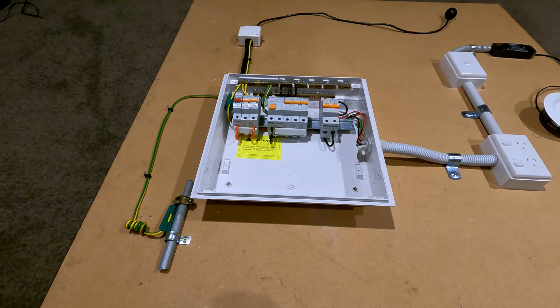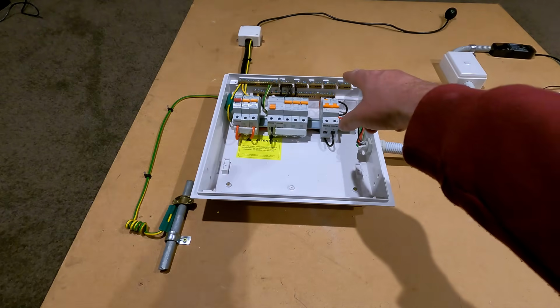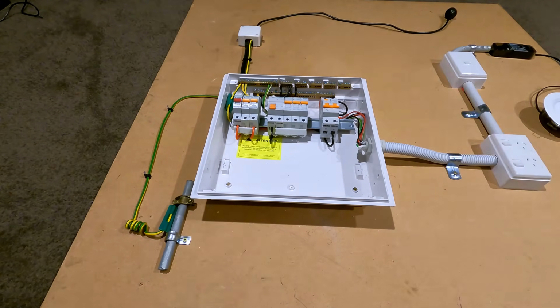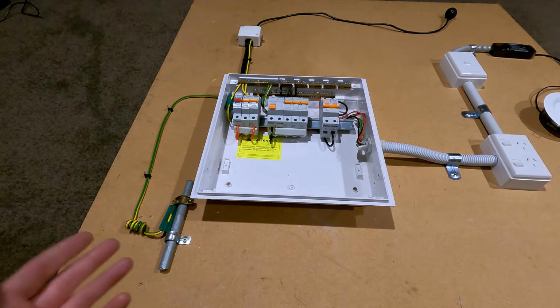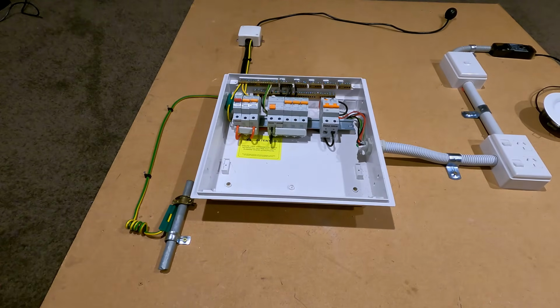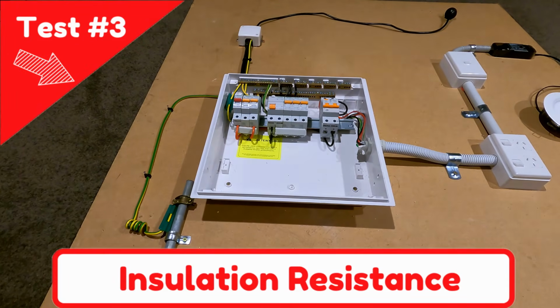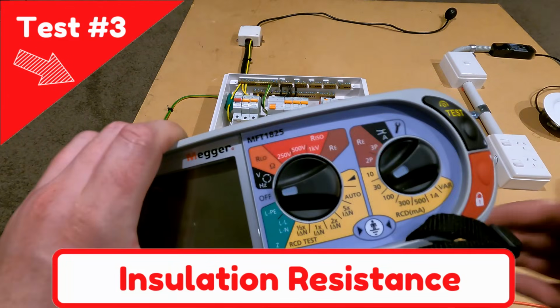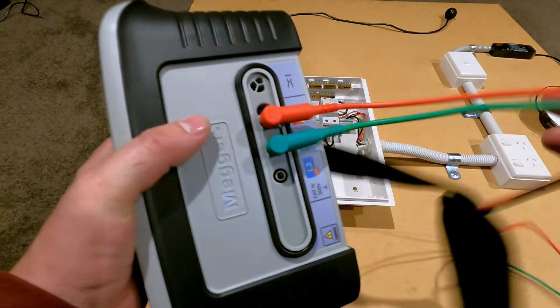Now that's the only thing I don't have set up. I could have used one of these RCD bars as an equipotential bond, but it's the same process. Just test between the two or wherever that bonding point is and ensure the resistance is less than 0.5 ohms. Now the next test, we want to do an insulation resistance test. So what you'll need for that is a multifunction tester and a couple of leads plugged into it.